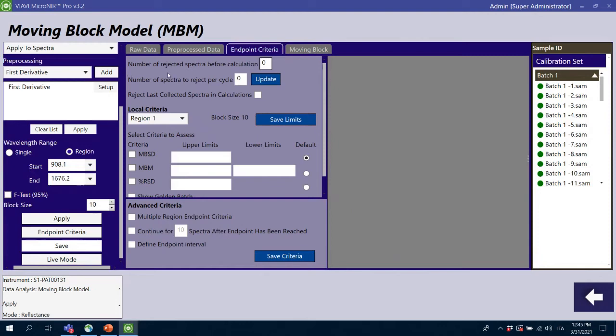First of all, in this software version has been implemented the capability to reject spectra that are not compliant with the spectra that we expect. And one thing is clearly to reject a certain number of spectra before starting the calculation. This is a function that has been requested by some customers, because in the beginning we normally have a big variability, and I would say senseless or not, I don't want to argue, but if you want to remove that big variability in the beginning, you can select a number here.